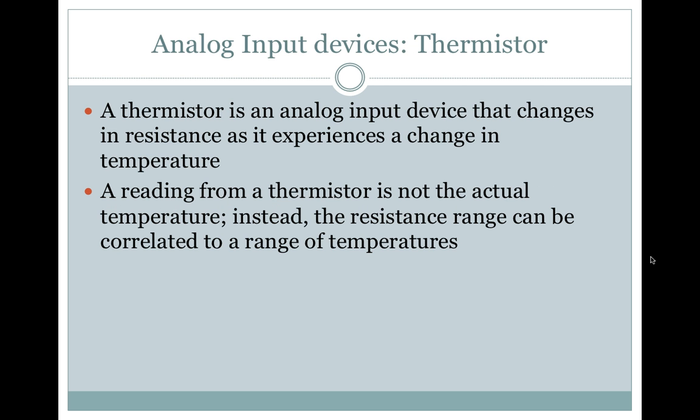Analog input device — thermistor. A thermistor is an analog input device that changes in resistance as it experiences a change in temperature. A reading from a thermistor is not the actual temperature. Instead, the resistance range can be correlated to a range of temperatures.